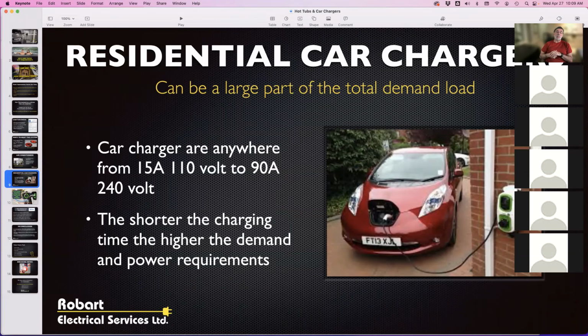Residential car chargers are the big one because they can be a large part of the total demand. Car chargers range anywhere from 15 amps to 90 amp 240 volt, and they're added to a load calculation at 100%. For example, we did a 12,000 square foot house north of St. Albert, and this gentleman had two garages in front with two 90 amp Tesla car chargers, one in each garage. The total service size for this residential house was 400 amps. All of these things are taken into calculation when figuring out how much power to bring into a house. The shorter the charging time for electric cars, the higher the power consumption, because there's more power being put to the batteries.